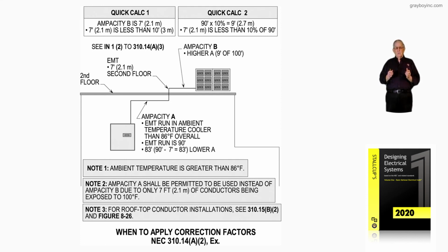you could walk into a Walmart or a Home Depot, and those conductors will be down in raceway systems, routed across the bottom of the joist down about 3 to 4 foot, sometimes even maybe 5 foot. They're getting those conductors and conduit down lower so that the heat that rises to the ceiling won't affect the heating of these conductors where ambient temperature is involved.